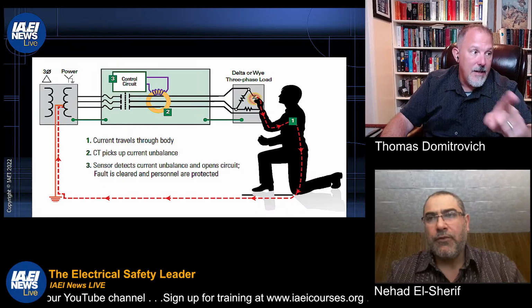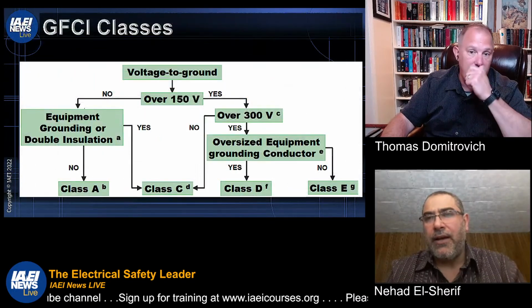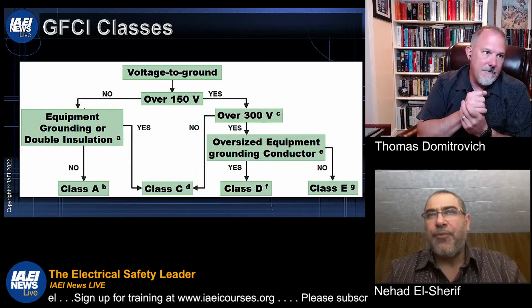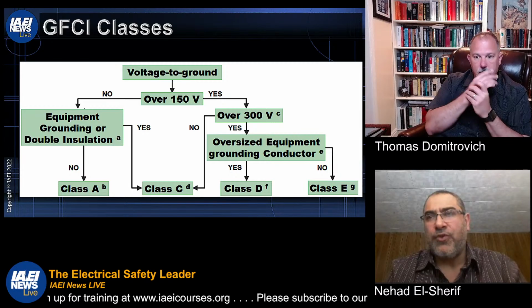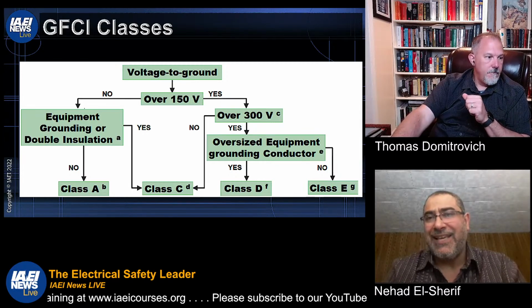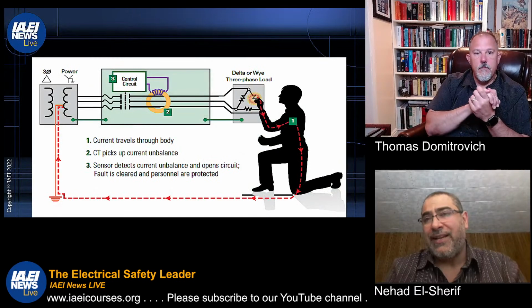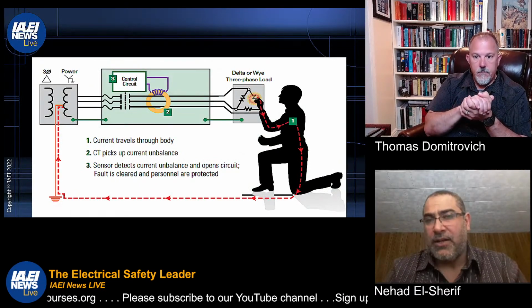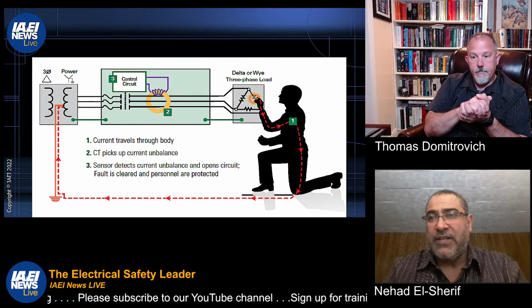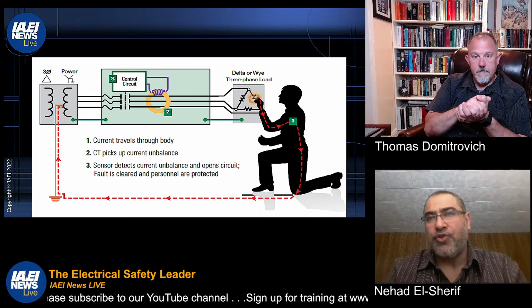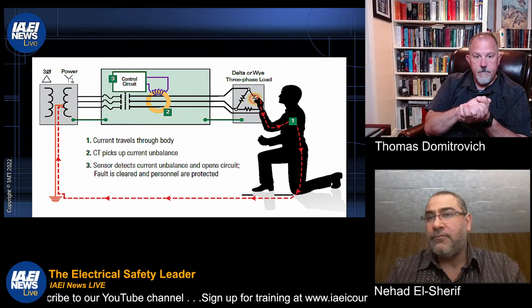Now, the next slide is your classes. So the point from the previous slide is to emphasize that Class C, D, and E are three-phase. You can get a three-phase and a single-phase Class C, D, and E. Class A GFCIs is only single phase, but in terms of the theory of operation, it's very much the same.